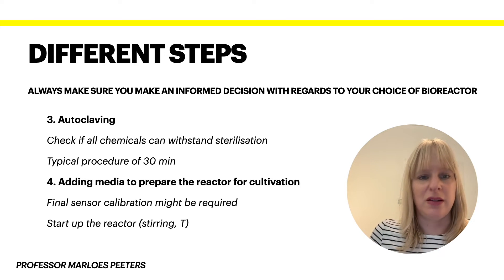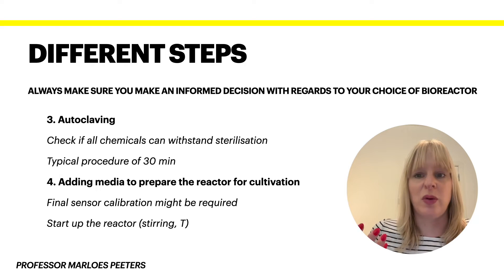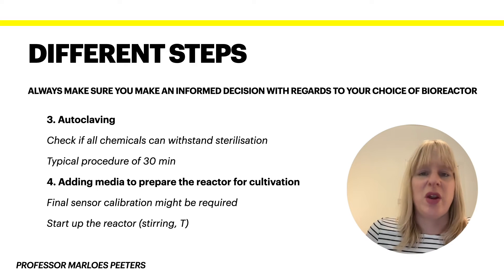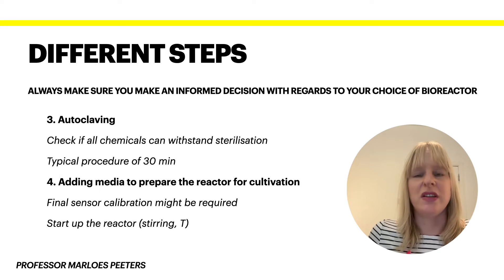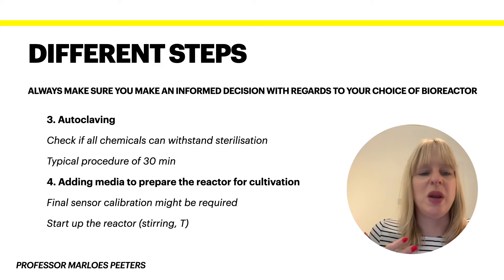In step four, after sterilization — and you may also need to autoclave some of the media — we can add the media to prepare the reactor for cultivation and start what we call the inoculation. This is the step where you might want to calibrate your sensors again, since some of them heavily depend on operating conditions. Having done that, with media in the reactor, we can start up the actual reactor — physically turn it on. We get it to the required temperature and start the stirring to ensure proper mixing. All of this is done before the inoculation, where you actually add the cultures.